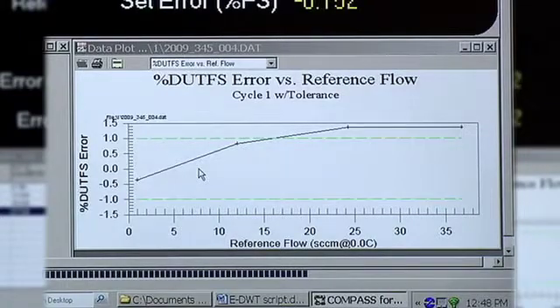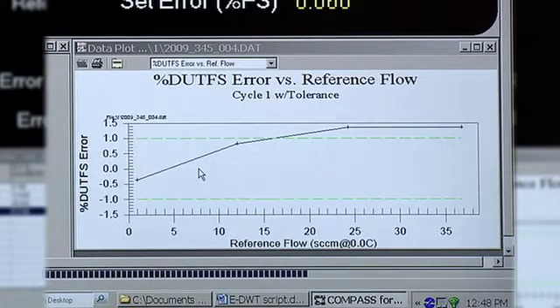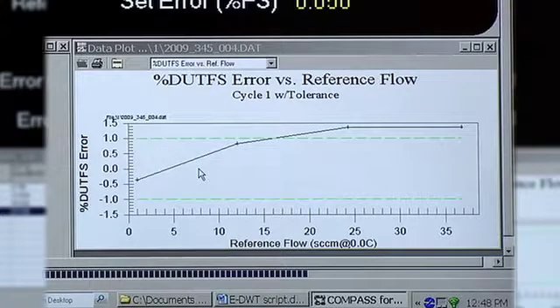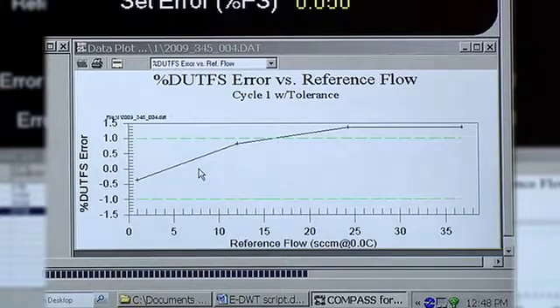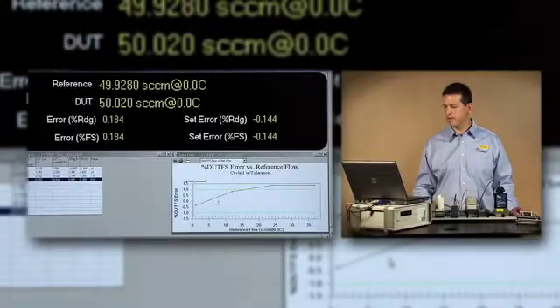Now this MFC, both on the third and fourth point, you can see we're out of tolerance and so it's going to need adjustment to bring it back into tolerance before returning to the field.